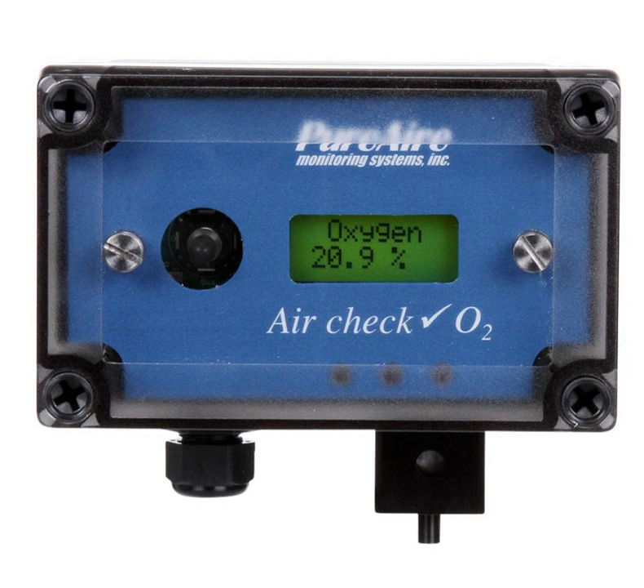Electrochemical gas detectors work by allowing gases to diffuse through a porous membrane to an electrode where it is either chemically oxidized or reduced. The amount of current produced is determined by how much of the gas is oxidized at the electrode, indicating the concentration of the gas. Manufacturers can customize electrochemical gas detectors by changing the porous barrier to allow for the detection of a certain gas concentration range. Since the diffusion barrier is a physical, mechanical barrier, the detector tended to be more stable and reliable over the sensor's duration and thus required less maintenance than other early detector technologies.